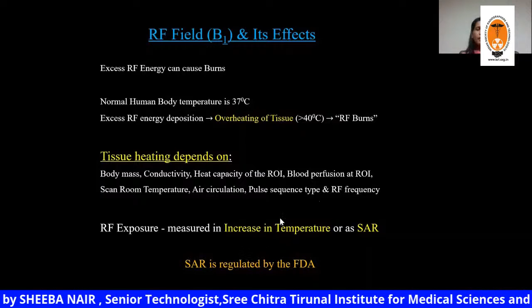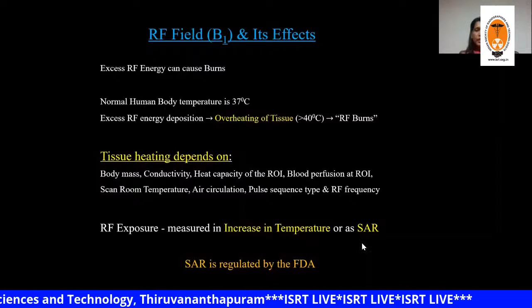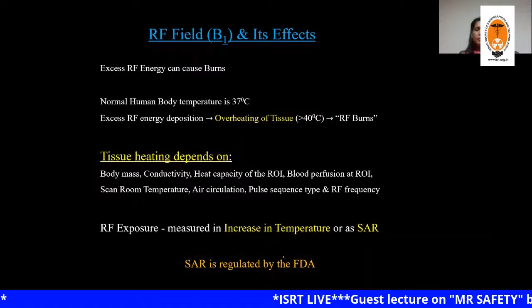So proper ventilation is very, very important in an MR room. We also have to select the parameters in such a way that they do not exceed the recommended limits. RF exposure is usually measured as the specific absorption rate, the amount of energy deposited per unit gram of tissue. The SAR, like radiation, is regulated by the FDA.